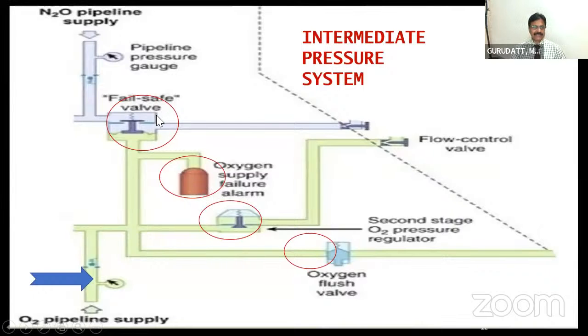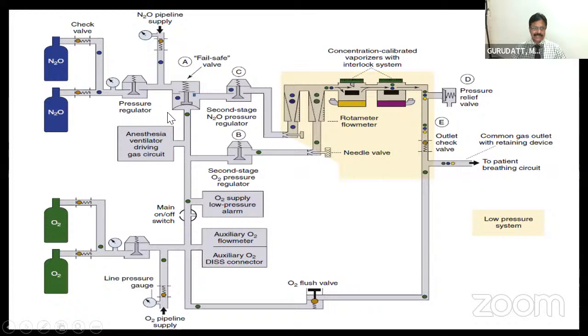So first thing, let me discuss about the fail-safe valve. Already I told you about these fail-safe valves which have replaced the master and slave pressure regulators of oxygen and nitrous oxide. So in the newer workstations, you have a separate fail-safe valve. The oxygen pressure has to enter into the fail-safe valve of nitrous oxide to open the nitrous oxide flow into the flow meter assembly. So these are the fail-safe valves.